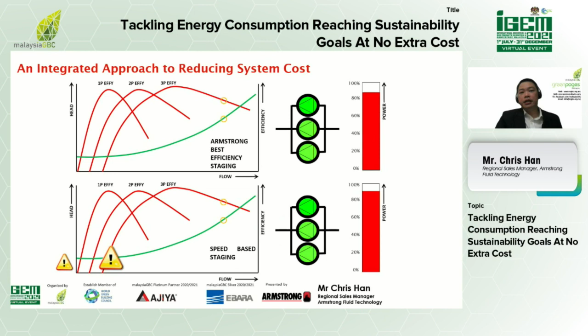Now, as I click through the animation, I want you to turn your attention to the energy bar on the right-hand side, the power consumption bar, which shows the energy impact of delayed staging, especially prominent in the traditional approach where the efficiency has fallen before the next pump stages on. So what this means is that with the best efficiency staging approach, during operation, you are saving energy while also meeting the demands of the building.